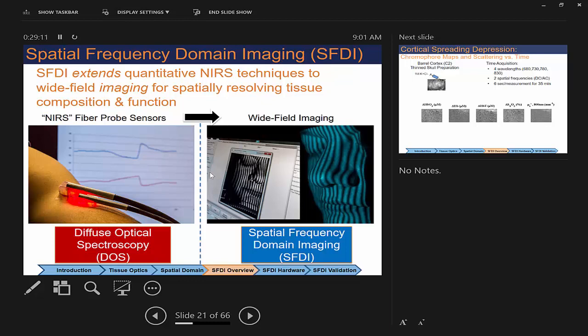Diffuse optical spectroscopy, or photon migration spectroscopy, or frequency domain photon migration, all different names for the same stuff, have a source and detector, but you modulate at many frequencies. You have a calibration approach that corrects for the instrument response function at every frequency, but you're limited to point measurements. Most of these devices are contact. A few have been developed non-contact, but if you wanted to create an image, you'd have to scan that probe, and that gets really cumbersome.